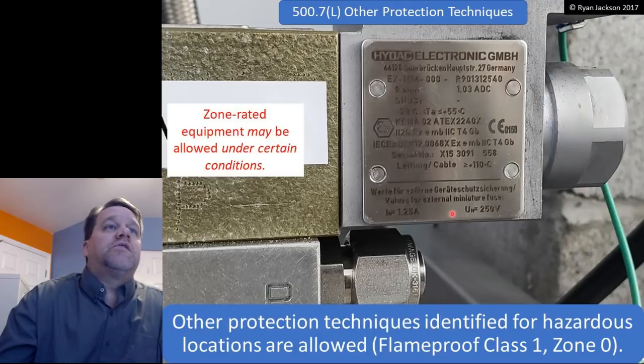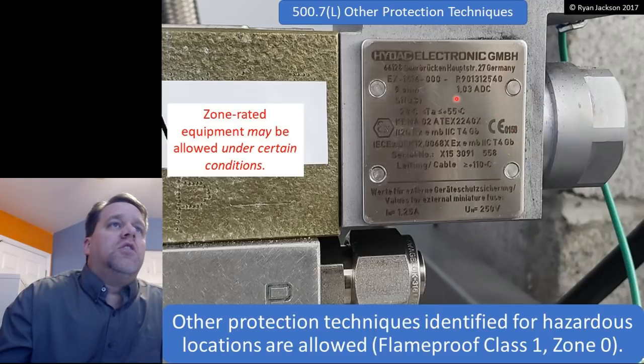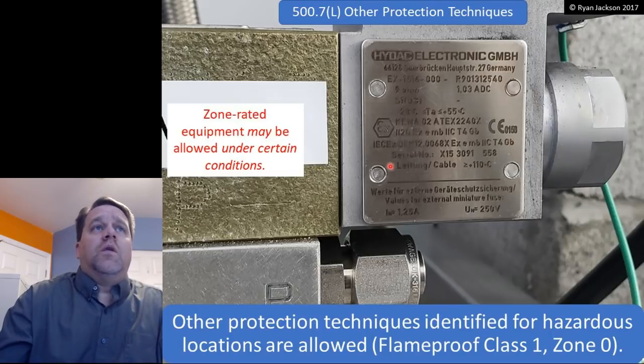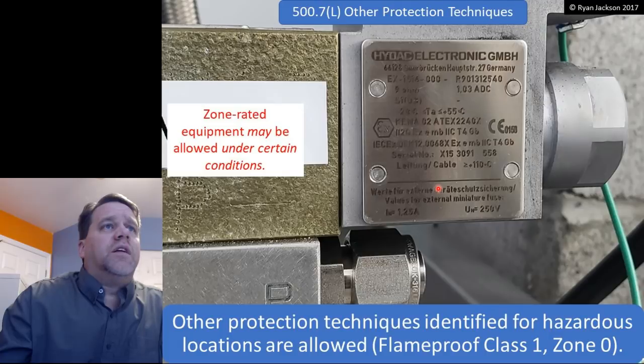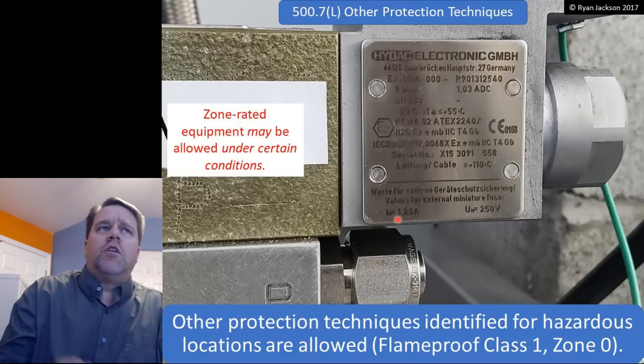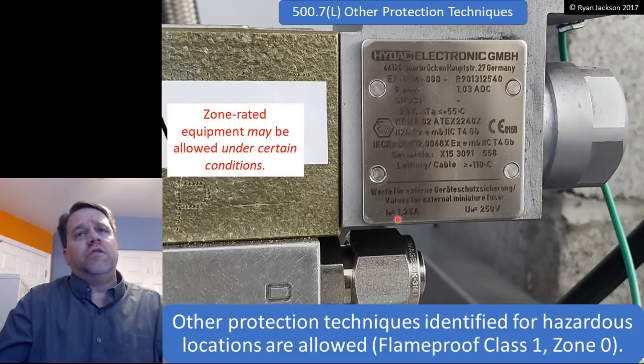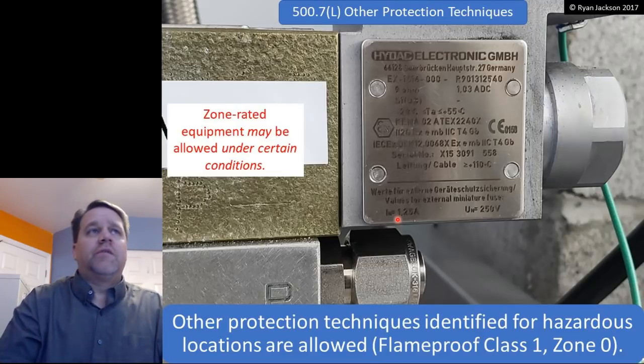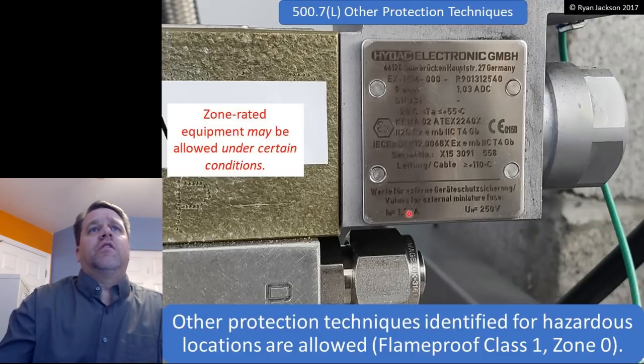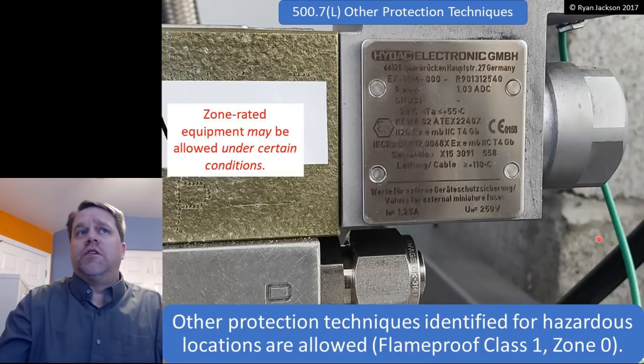So looking at this piece of equipment, you can see that the marking is very different than what we would see here in the US under a normal NEC regulated installation. This is ATEX rated equipment, and I mentioned earlier, you can only use zone-rated equipment if it bears the mark AEX. And even then, you're limited on how you can use it. So that's item L, other protection techniques.